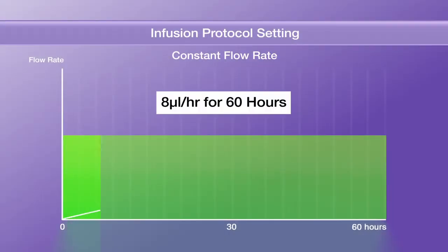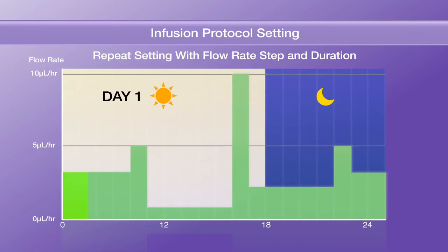Infusion protocol setting. This setting allows for a fixed constant infusion for the duration of the study or a combination of different flow rates and durations to be programmed. With repeat setting and the use of different flow rates and durations, advanced infusion protocols like circadian rhythm profiles may be programmed as shown in the video and graph. Test compound administration begins after configuring and saving this infusion protocol into the embedded memory in the pump. You can configure up to 16 discrete infusion steps between 0 and 10 microliters per hour.